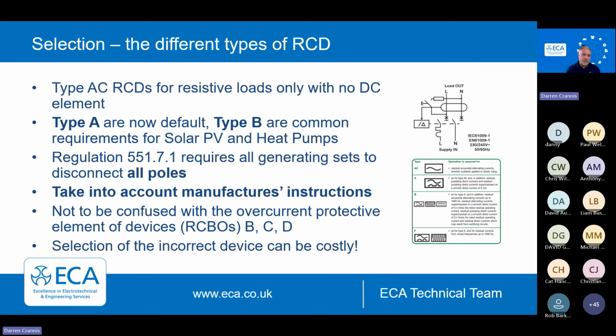When it comes to specifying RCDs for equipment, we should take into account the manufacturer's instructions. And we do that in BS 7671 because we're allowing manufacturer-specific innovation products to let us know that there might be some additional information that we may need to safely put that equipment into service. So we do allow innovation in BS 7671, and part of that is allowing the manufacturers at times to guide us, but they are a consideration, and sometimes the considerations may be onerous, that they may not make any engineering logical sense, or there may be other ways to achieve the same level of safety. So that's why we say that manufacturer instructions shall be taken into account.